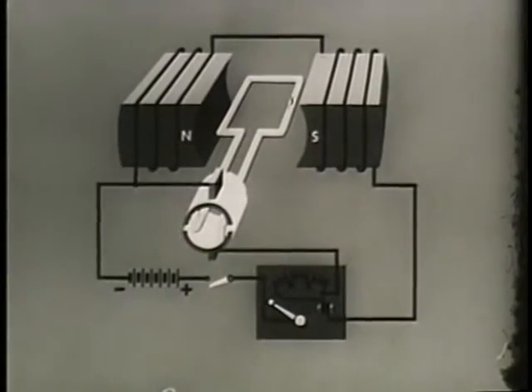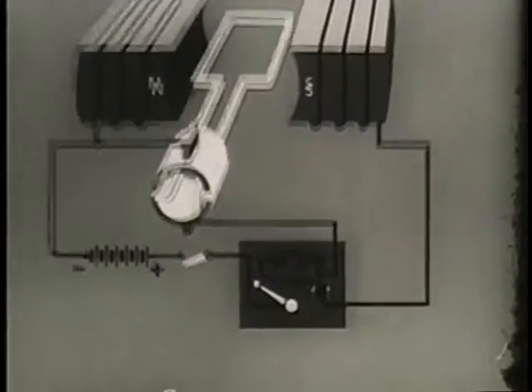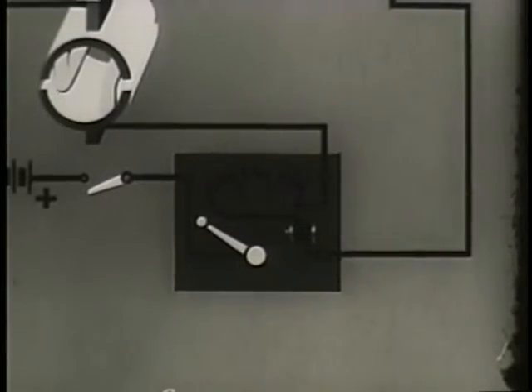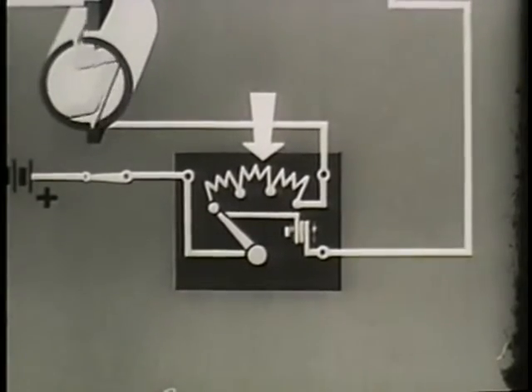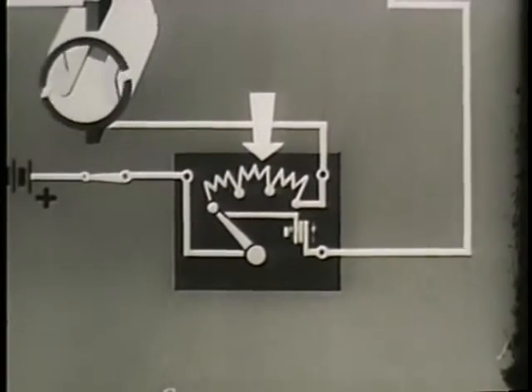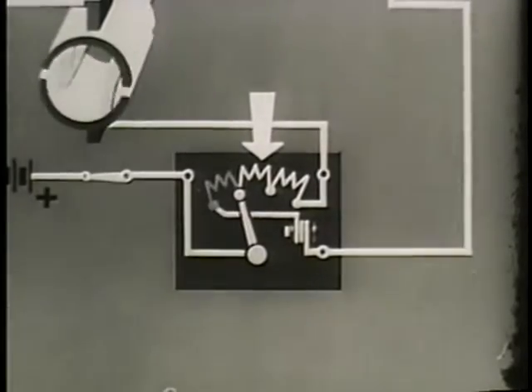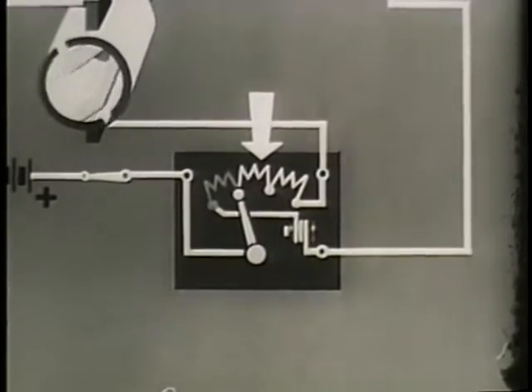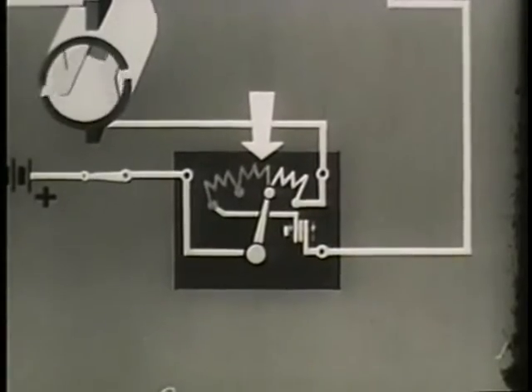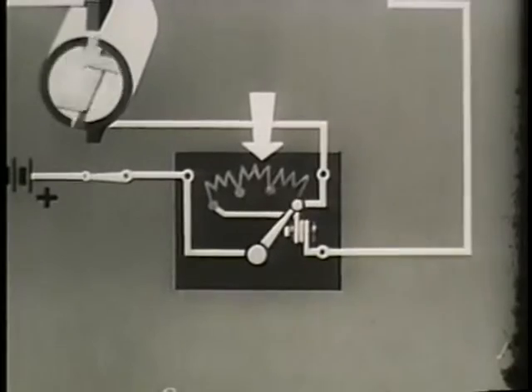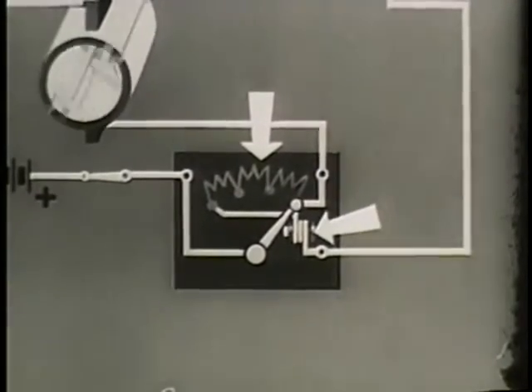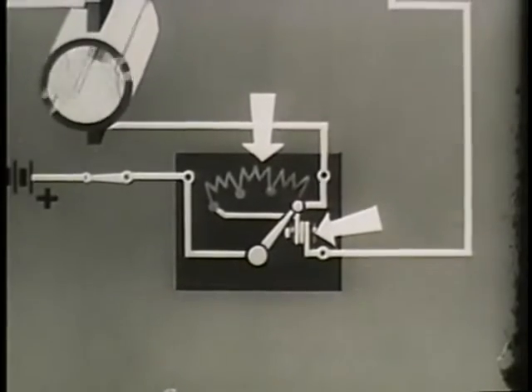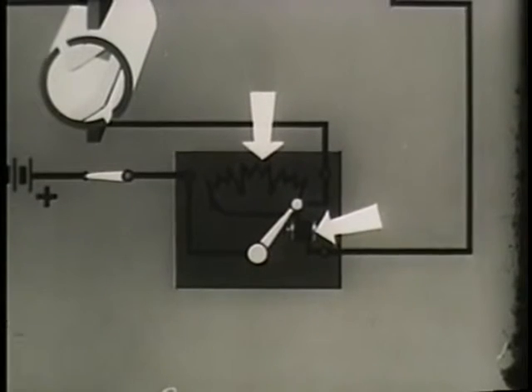Starting boxes are used with DC motors to avoid the application of full current before the CEMF is built up. In the starting position, the circuit to the rotor windings is closed through a series of large resistance coils. As the lever of the switch is moved, rotor speed and CEMF build up gradually and the resistance coils are subsequently cut out until running speed has been reached. The lever is held in the fully open position by an electromagnet. If for any reason the power should fail or the field coil open, the electromagnet becomes de-energized and the lever is returned to the starting position by spring action.